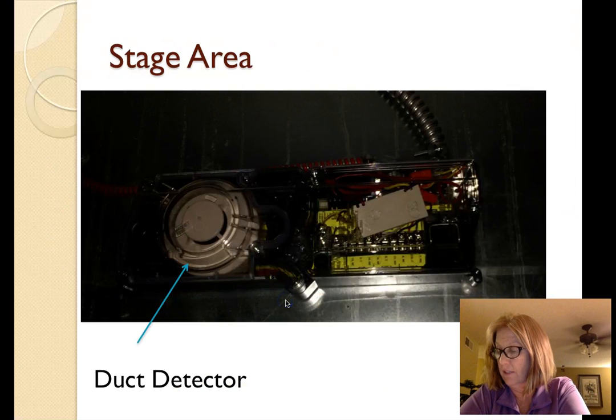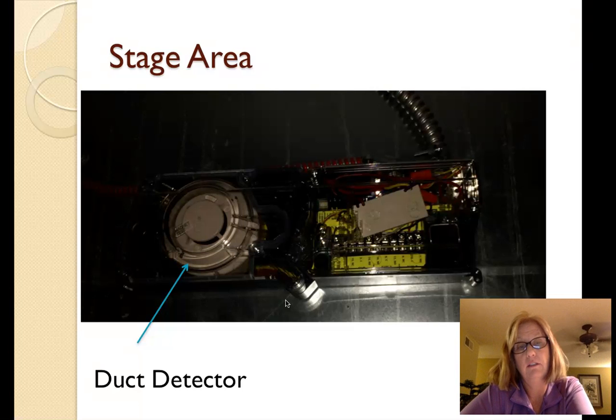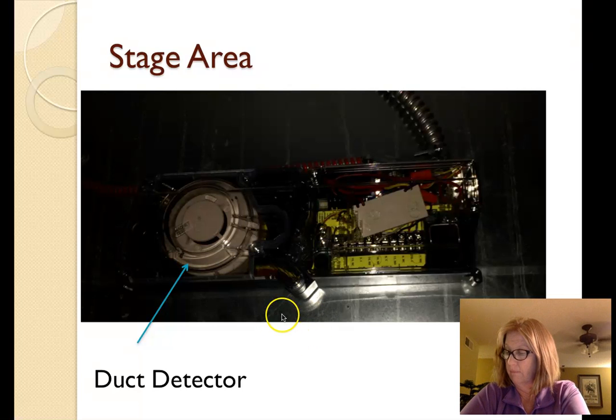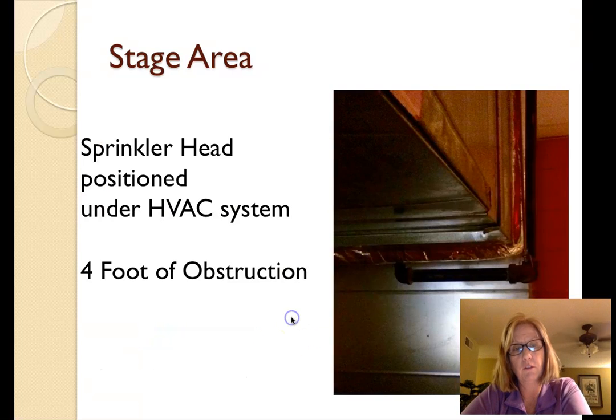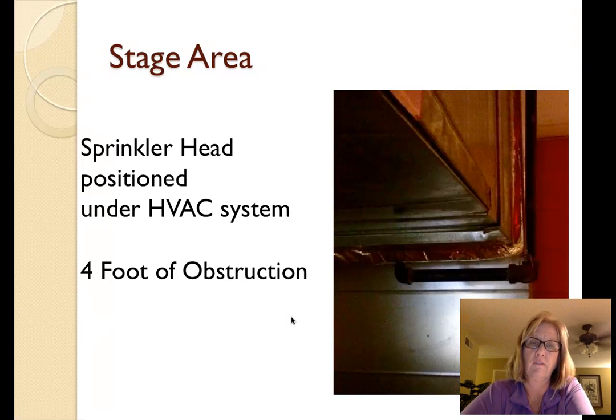Then we went to the stage area. Behind the curtain, there was ductwork that had a duct detector in the HVAC system. And it also had an interesting feature, which was a sprinkler head that was underneath the HVAC system. Inspector Ellsworth said that sprinkler has to be positioned there because this is considered an obstruction over 4 feet, and per NFPA 13, it must have a sprinkler head underneath it.